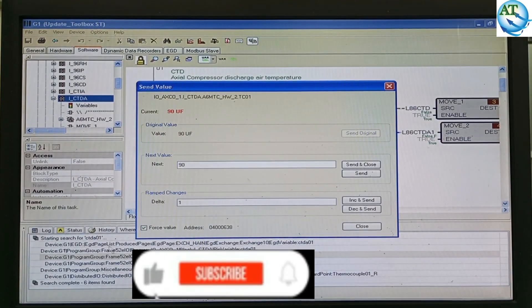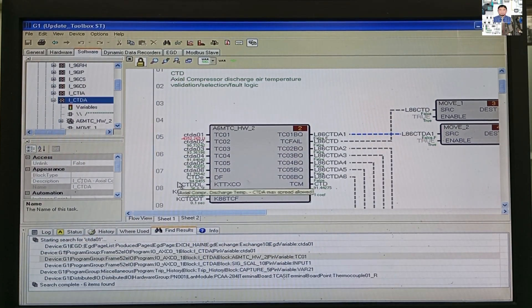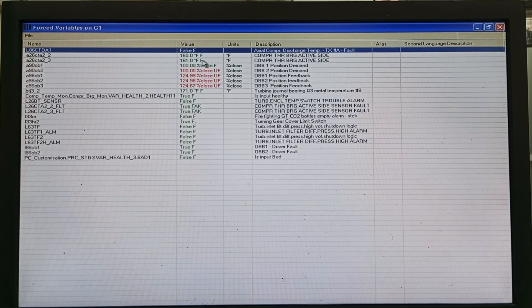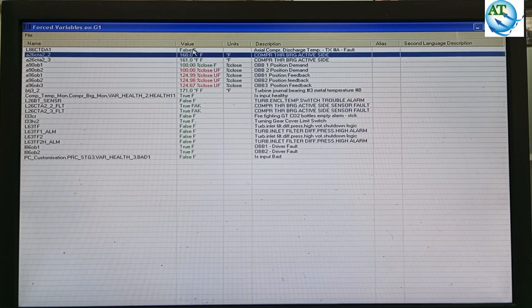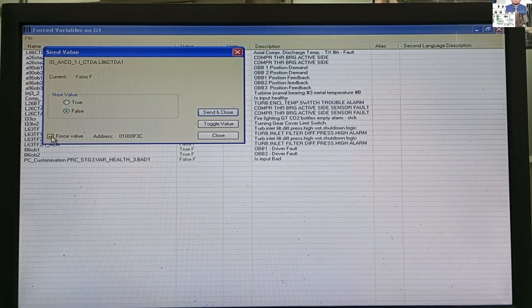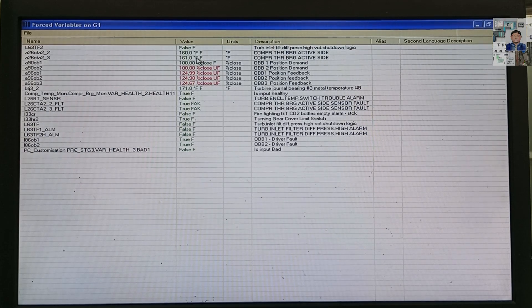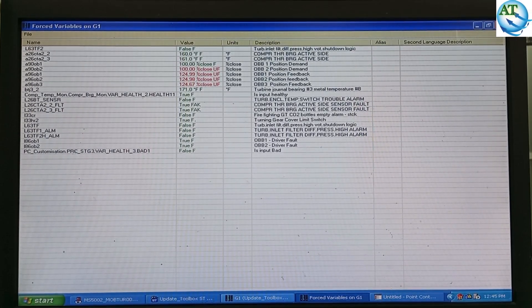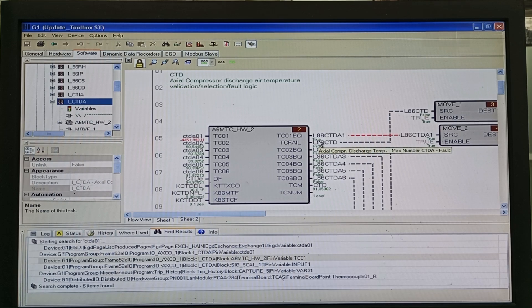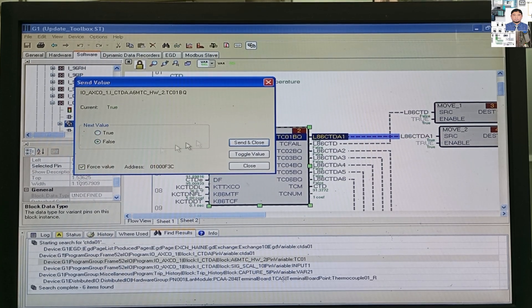After completing your work and changing the element, you can remove the force value and press Send and Close. The value will return to normal. In the list, you can see it is no longer present — it is already unforced. The healthy system force is also removed. You can make it unforced, then press OK. Remove force value and Send and Close — it is also removed and is not present in the force variable list. In the block system, you can see all values have returned to their normal state, as they were before. Now I will also show force removal from the block diagram system.